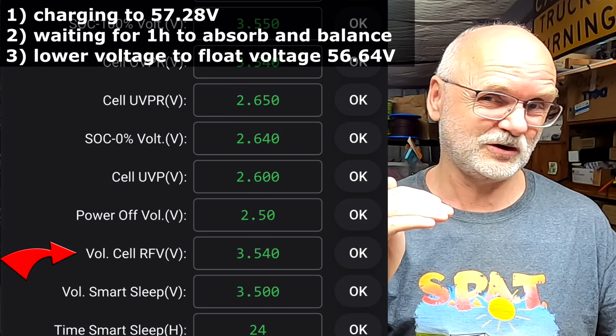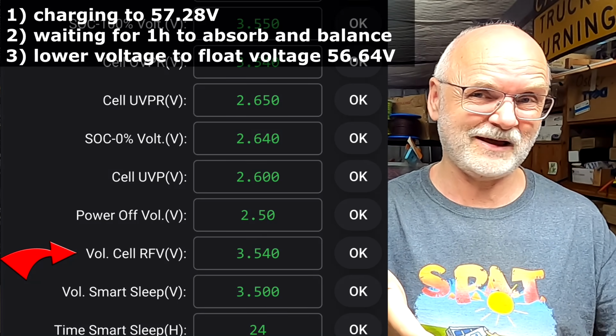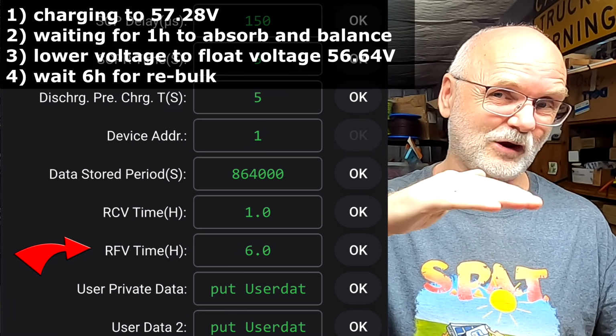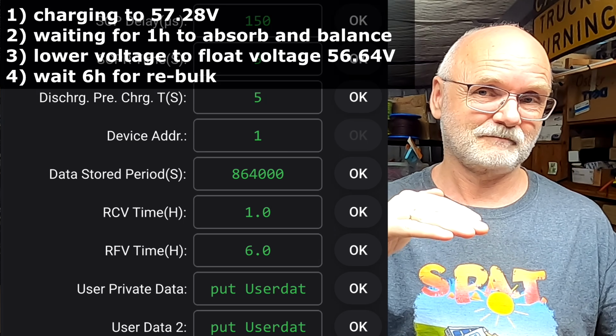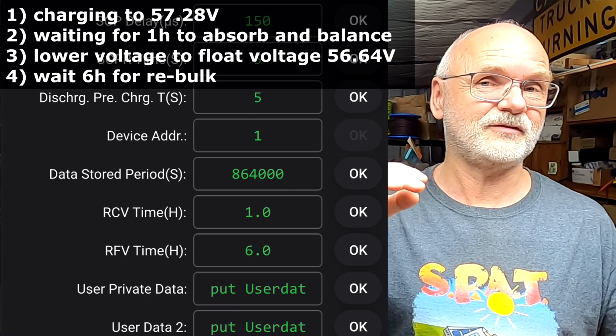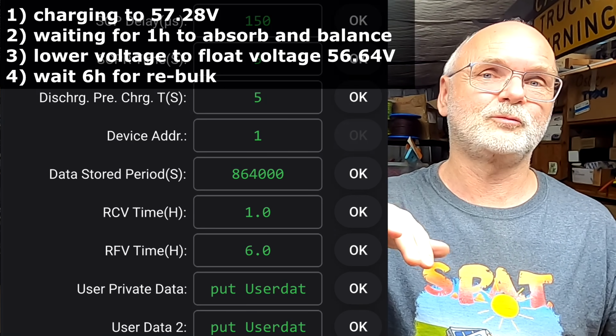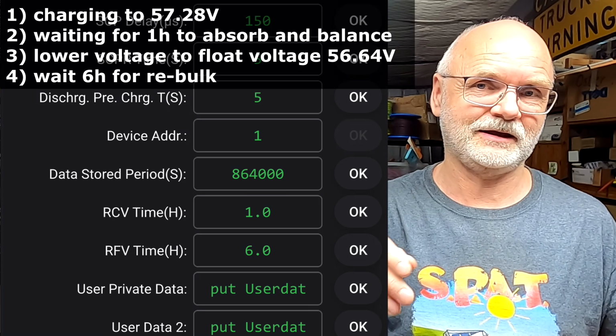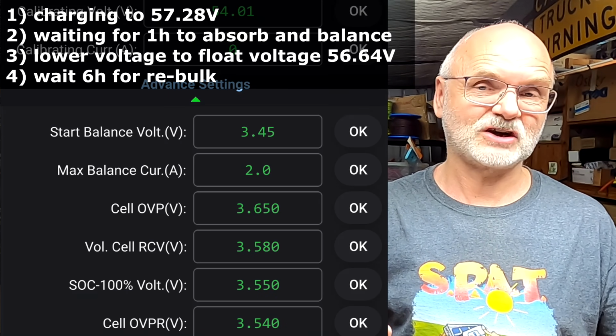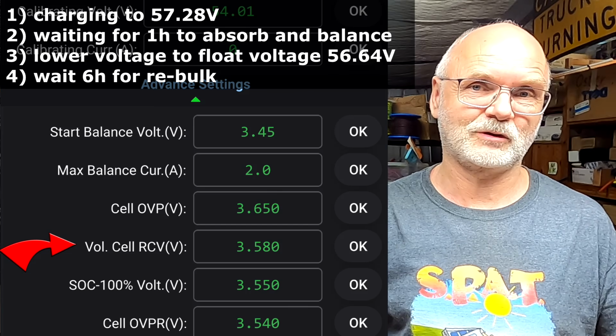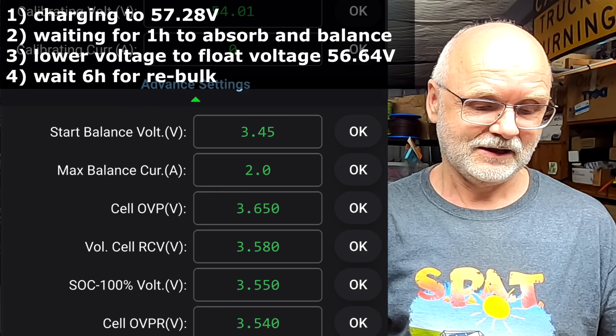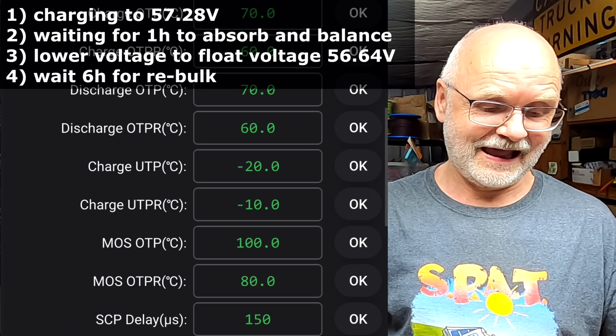It lowers your voltage to whatever you set in the BMS now. And then it stays in this float voltage for 6 hours. After these 6 hours, if there is still sunlight out there, it would start another charge cycle and charges to your cell RCV, the requested charge voltage again. And you can set this timer as per your needs.